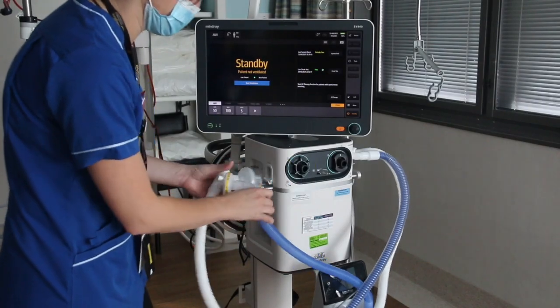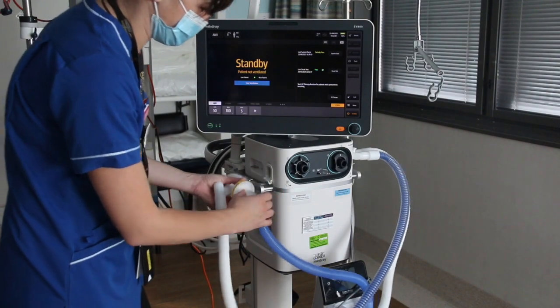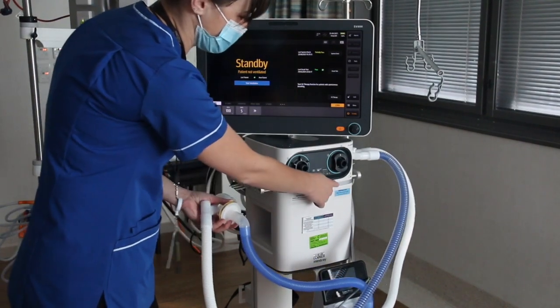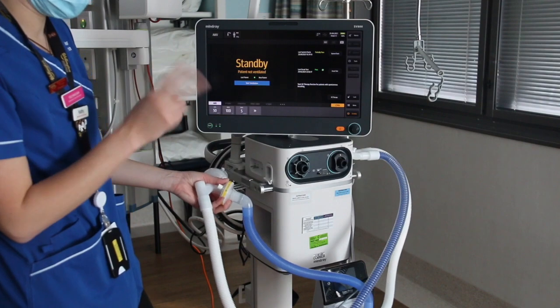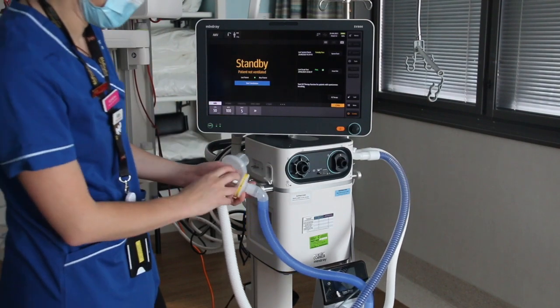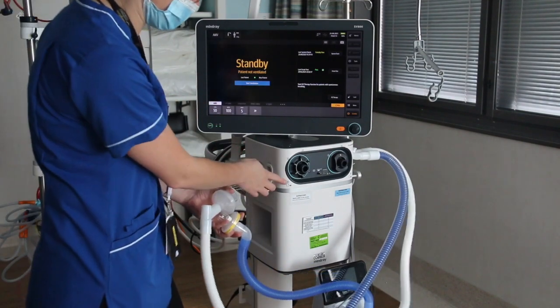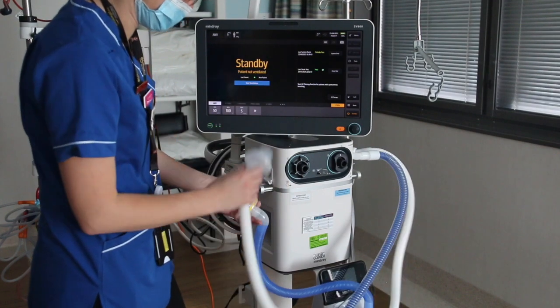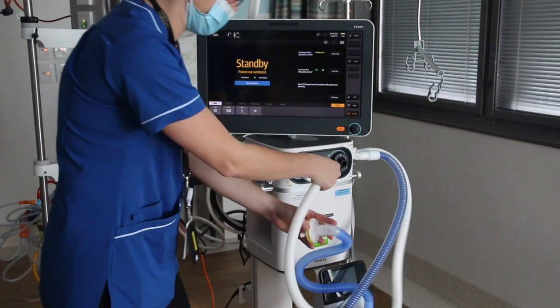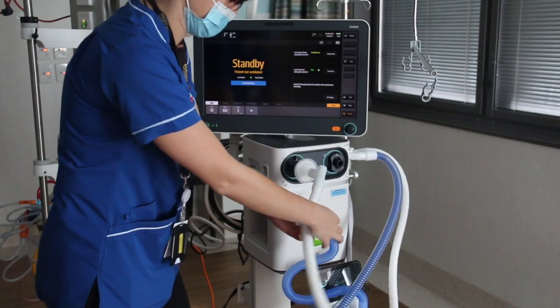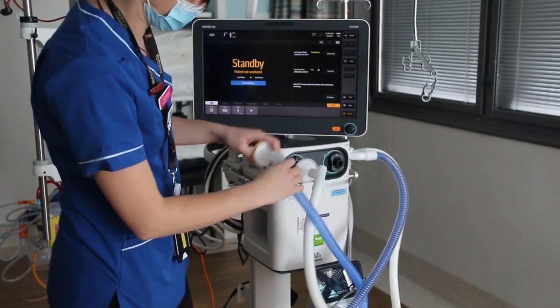Then with the tubing, another really important point is that the expiratory limb and the inspiratory limb on the Mindray might be around the opposite way from ventilators that you're used to. The exhalation limb, there's a little picture of a person breathing out here, so you want your white limb attached to the exhalation on this side. Then on the other side, your inspiratory, your blue limb.